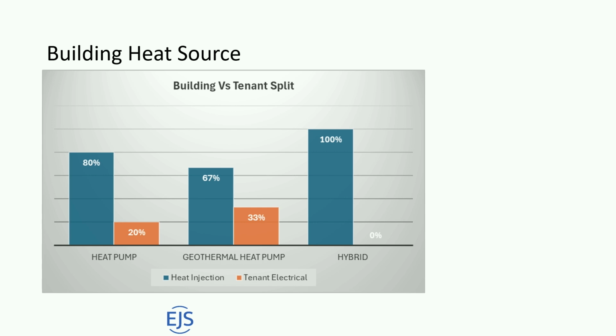In a conventional heat pump system, 80% of the utility and 100% of the system is at the building level. So that's your boilers and your towers and your pumps and your heat exchangers and your glycol feed and everything that goes into the utility side of maintaining that loop between 60 and 90 year-round. 20% is at the heat pump level, so in the apartment. So 20% of the utility is running the compressor in the apartment and the fan and the electrical components.